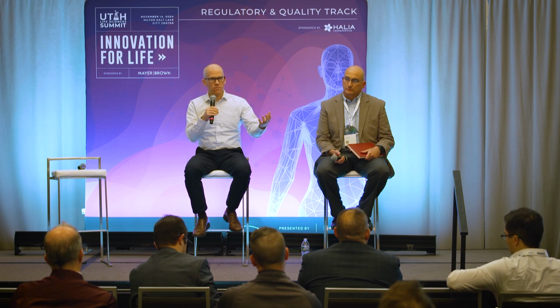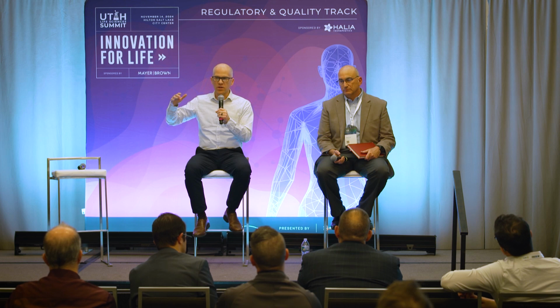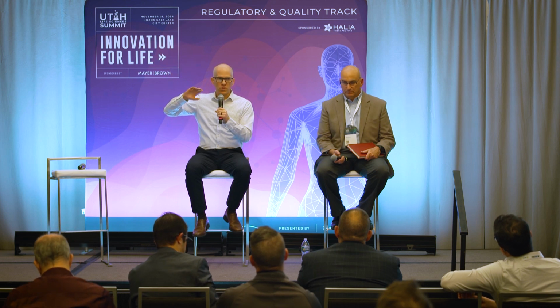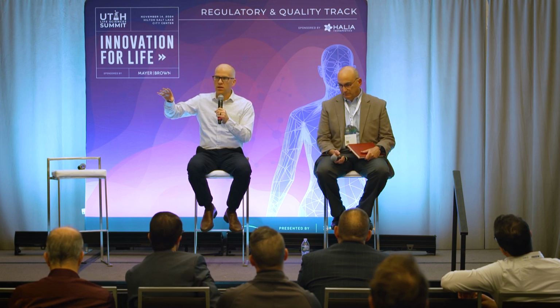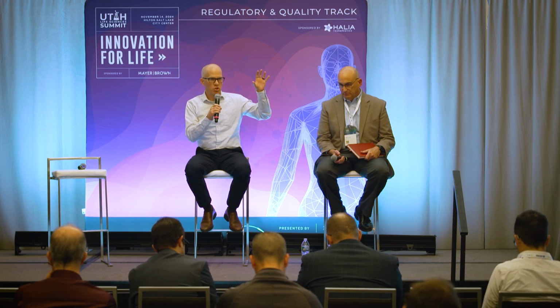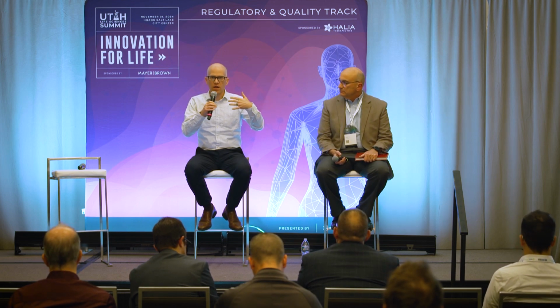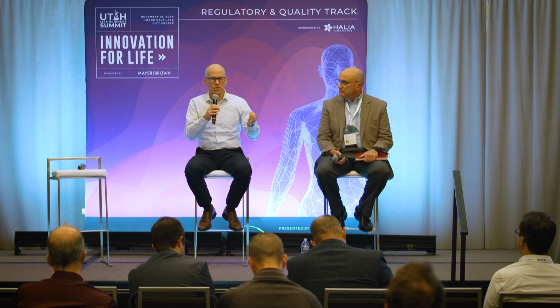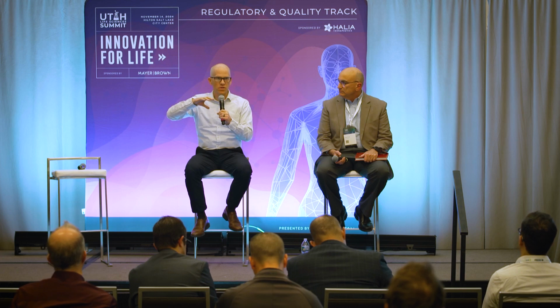This is a difficult topic, because if you Google how to create a cybersecurity risk analysis or a cybersecurity threat model for a medical device, you'll see one blog entry that says risk analysis is risk analysis, you need to follow 14971, and your cybersecurity risk analysis should follow that. Then you find another blog that says cybersecurity risk analysis is fundamentally different than safety risk analysis, so you should not be following 14971. There's a lot of confusing information out there, and like most things, it's a combination of both. Safety and cybersecurity risk analysis are two fundamentally different things, but they do follow similar processes. And as we talked about, you need to be thinking about your cybersecurity not only as a product, but throughout its entire life cycle.